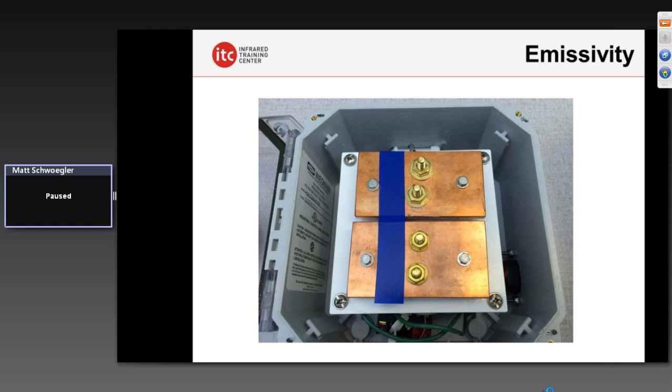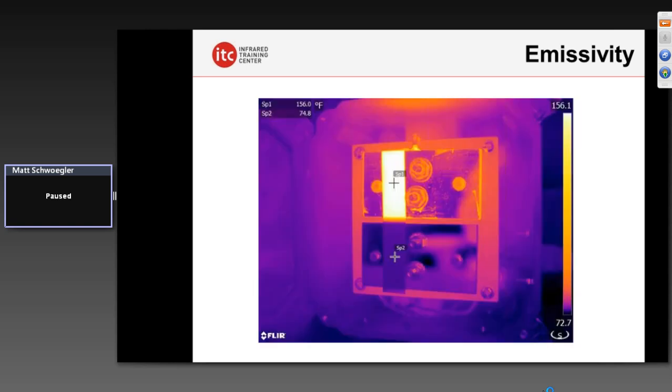If I put a piece of electrical tape across the two — this is just regular Scotch 33, which has a good, known, consistent emissivity of about 0.95 or 95%, meaning it's very good at radiating its energy off its surface — and if I put that across those two phases of bus, here's what we now see for apparent temperatures. It's not a 5-degree temperature difference. It's about a 70- to 75-degree — perhaps even more — delta T between the top phase and the bottom phase. That's huge, and that's something we have to stress: you have to know what you're doing and understand the physics behind what these cameras are seeing, because oftentimes objects will lie to you.